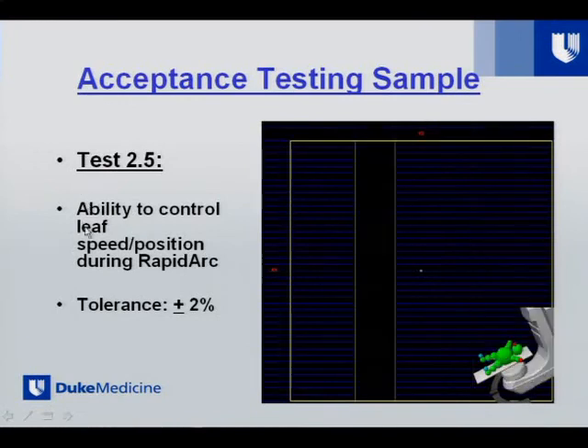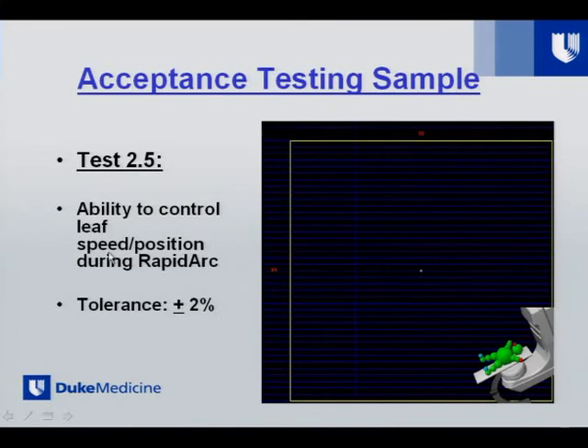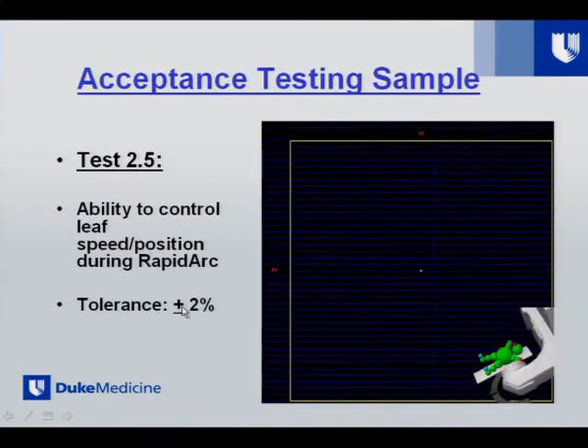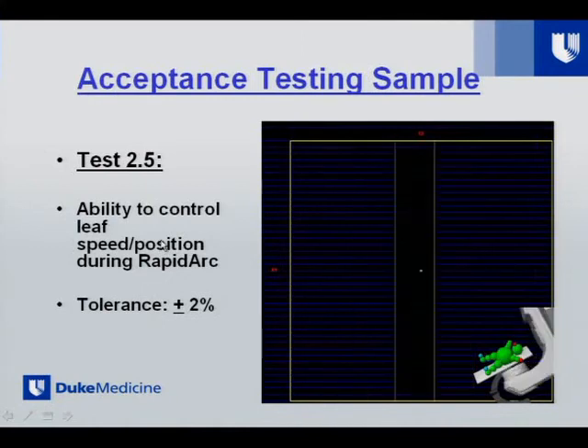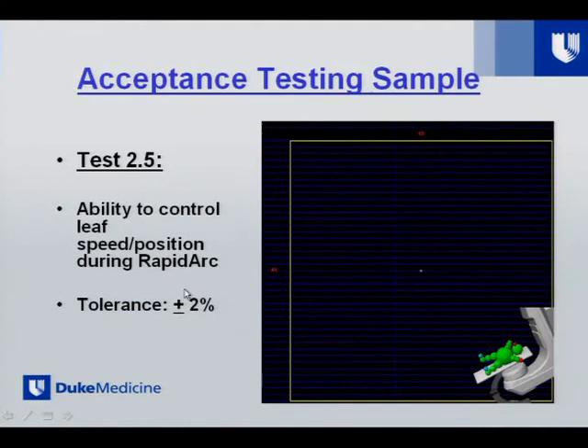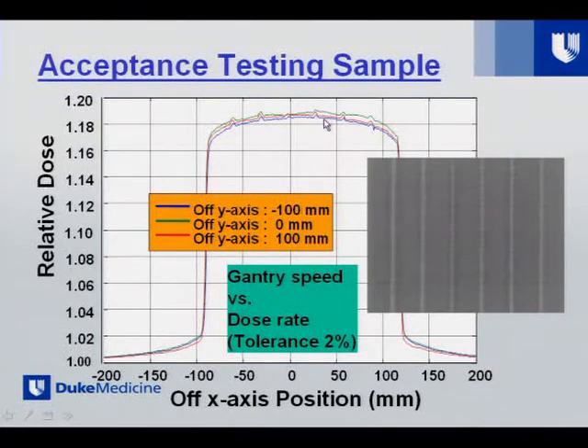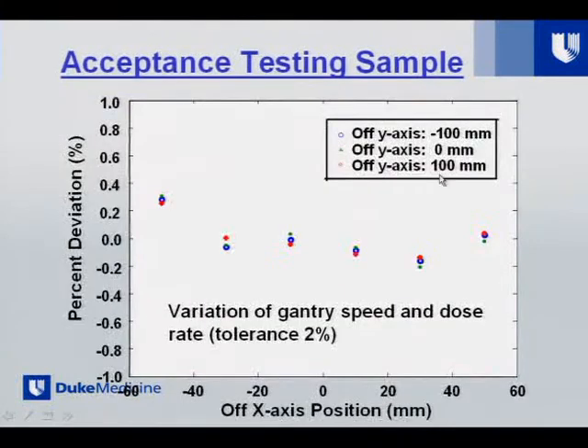We also test dosimetric accuracy — specifically the accuracy of dose rate versus gantry speed during Rapid ARC. As the gantry rotates with the slit moving at different speeds controlled by the prescription of each field, we verify control of leaf speed and position throughout. Tolerance for dosimetry is plus or minus 2%. We plot picket fence images and verify gantry versus dose rate tolerance within 2%.